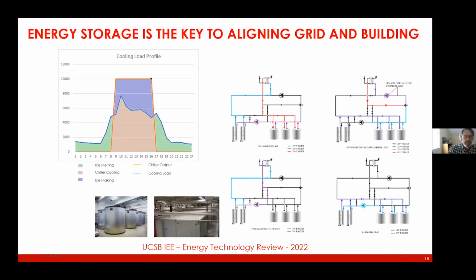But in a decarbonization scenario, it works differently, because we're going to do all of our refrigeration during the middle of the day when the sun is out, and we have significant photovoltaic contribution either to the grid or to the building or both. And then once we get outside of this period when the sun is shining, we're going to do all that cooling with the ice we made up here. A completely different scenario. No longer managing congestion, but now trying to shift our electric consumption to periods of time when the sun is out and the PVs are producing.